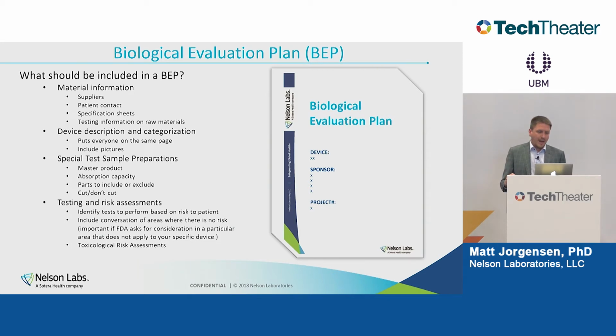So we have this example I just gave with the ASTM grade titanium. We do see that occasionally, and sometimes it works. With a really well-known material and good cleaning information, the FDA will sometimes say, okay, we understand this material is biocompatible, and let it go. So the biological evaluation plan is a great place to get that buy-in from the FDA.